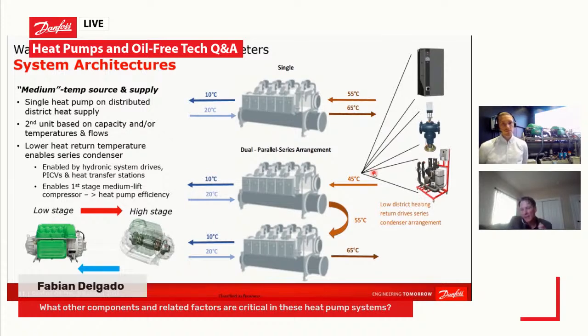What I mean by that is those hydronic systems were designed for three-way valve systems, which were in turn designed for constant speed pumping systems. If you apply a variable speed pumping system to a three-way valve-based demand-side system, then you're not going to get any of the benefit from that variable speed drive, because you're just bypassing all the flow around that three-way valve and maintaining the same flow of the system. So implementing pressure-independent control valves, two-way valves, to throttle that flow associated with the demand-side load becomes very critical.